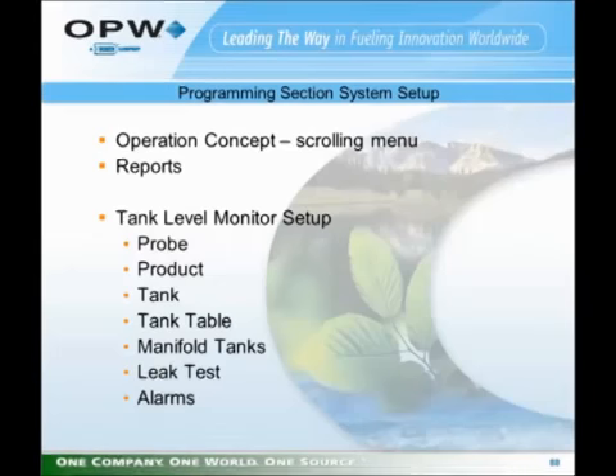As mentioned before, it's a scrolling menu for the programming of the unit. As an example, if you get into the setup to program the setup, you can navigate to the tank level monitor setup, and when you enter the tank level monitor setup, the submenus that you would then see would be probe, product, tank, tank table, manifold, tanks, leak test, and alarms. When you get into each one of the submenus, that's where you would program individual devices and individual settings.